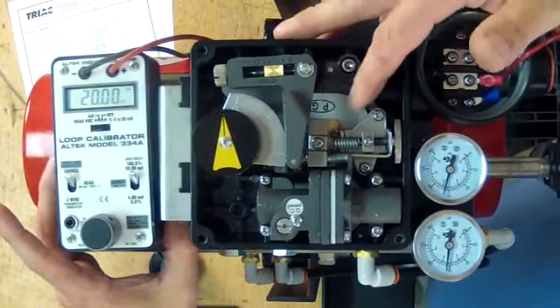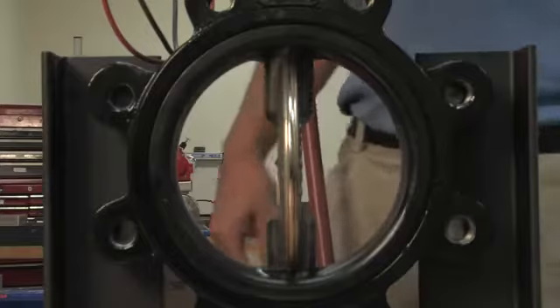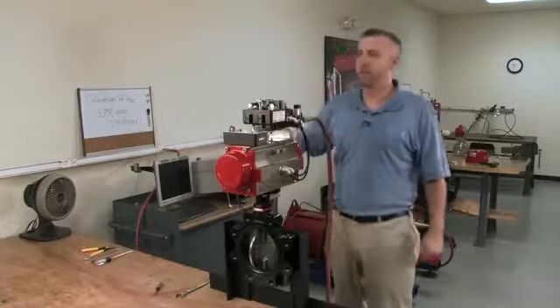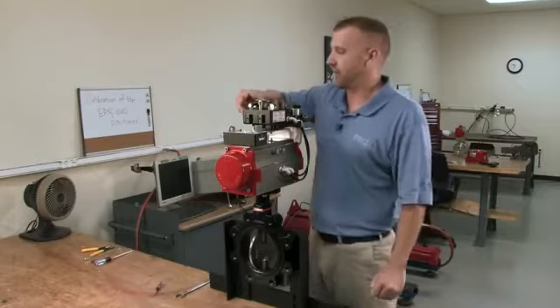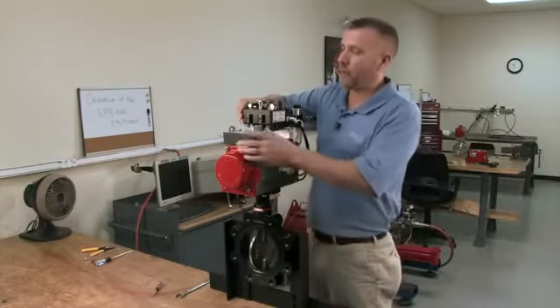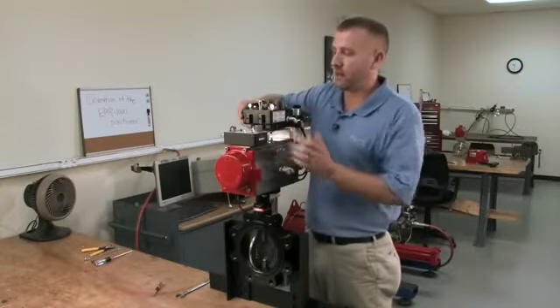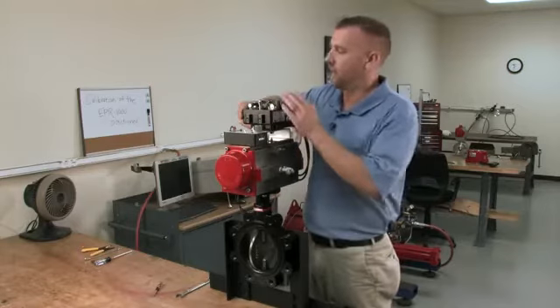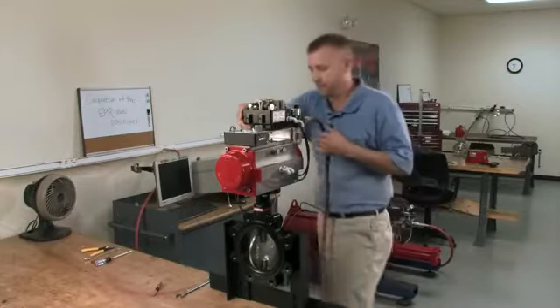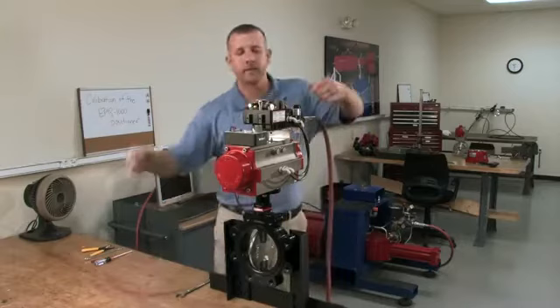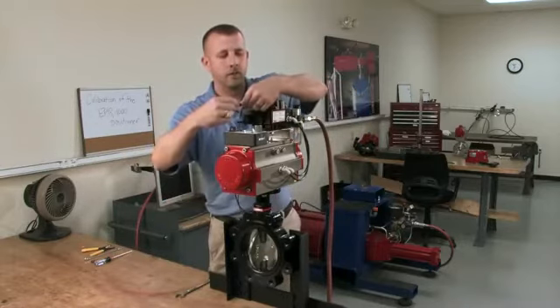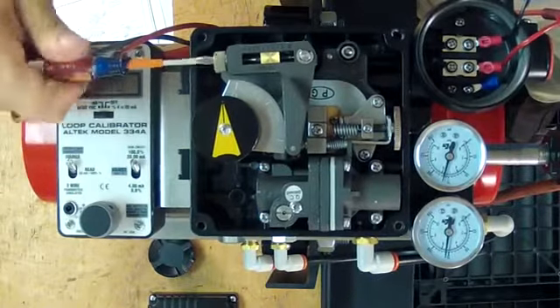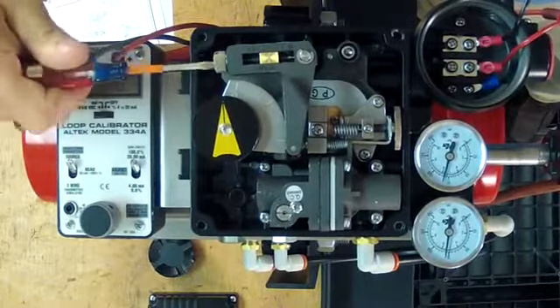And check with our counterweight. It looks good, but I know because I adjusted this that it is open way too soon, meaning at 15 milliamps this package is open. So we have to adjust the span back out of this package. By doing that, you adjust your span screw towards the negative. There's too much span in it.